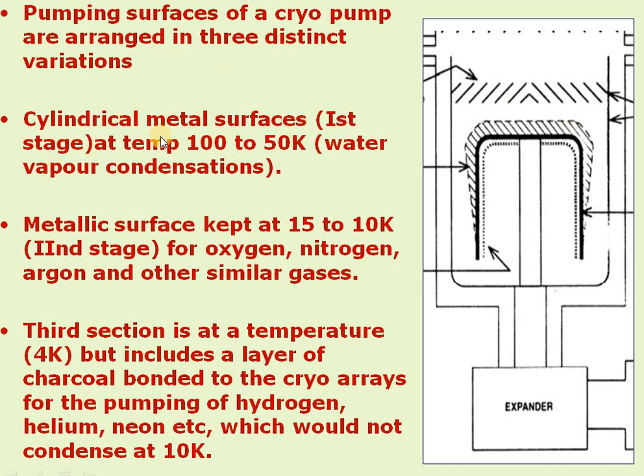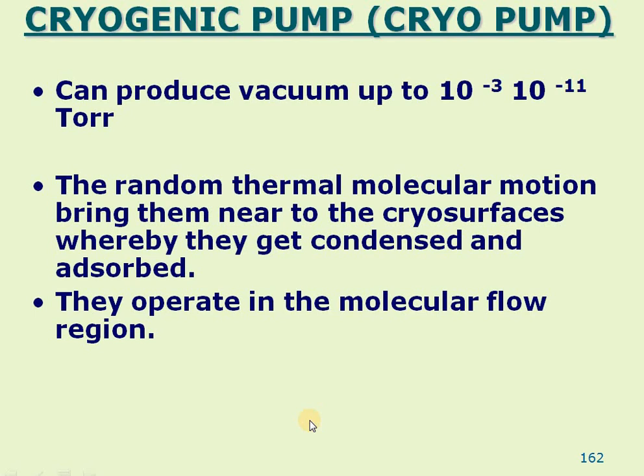This three-stage pumping process operates in a cryogenic pump. The first stage uses cylindrical metal surfaces kept at 100 Kelvin, gradually brought to 50 Kelvin for initial deposition. The second stage deposits oxygen, nitrogen, and argon by entrainment. The third stage at 4 Kelvin uses charcoal on steel surfaces to catch all remaining molecules. This pump can generate pressures ranging from 10⁻³ Torr to 10⁻¹¹ Torr.